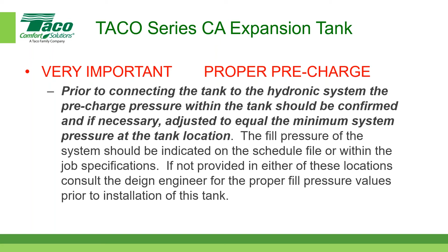That information—and Rich has defined this before, he's been a consulting engineer—should be on the schedule or within the job specifications. If you're a contractor and that's not available, you've got to go get it. I can't emphasize this enough. Moving on: the pre-charge—invariably, if you want to ruin a bladder or waterlog a tank, or worse, don't set the pre-charge to the correct number.